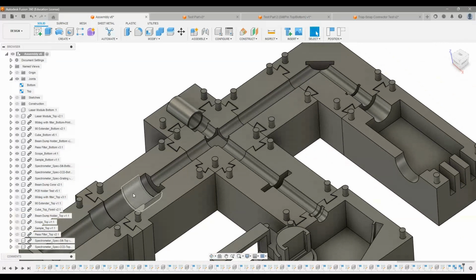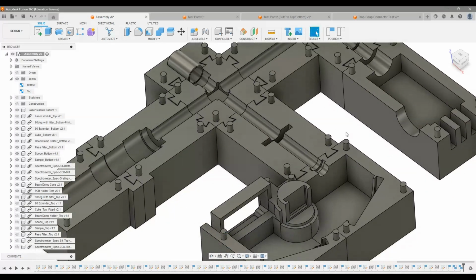So after the light is focused on the sample, that reflected scattering comes back through the cube and towards the notch filter segment. Here, there will be either a 550 nanometer long pass filter or a 525 nanometer short pass filter, and these can be used to view both the Stokes and anti-Stokes Raman scattering.